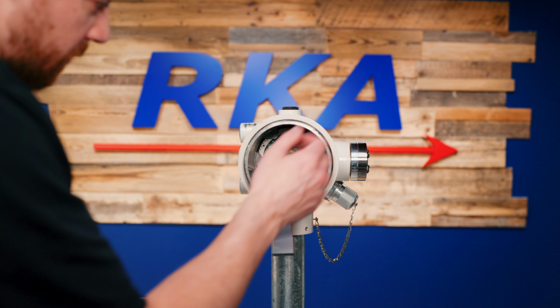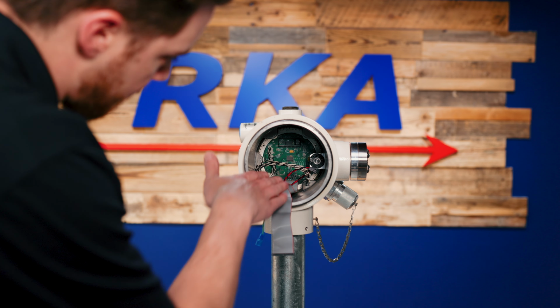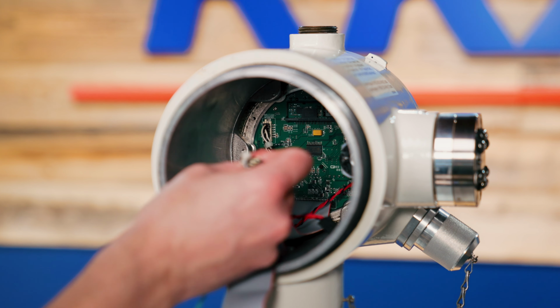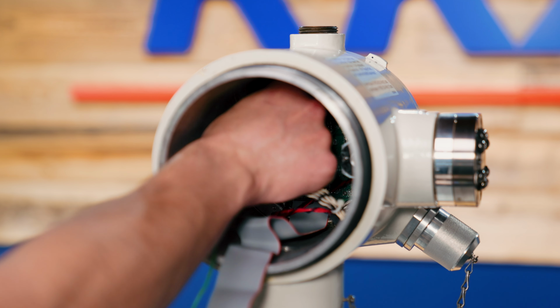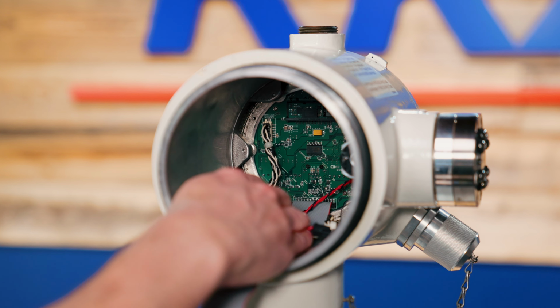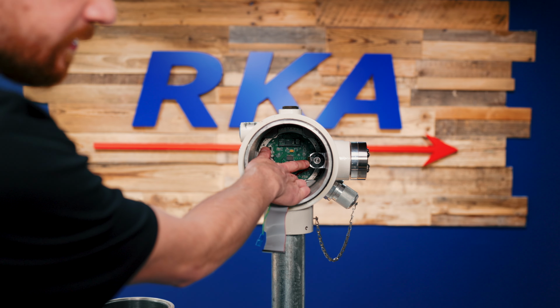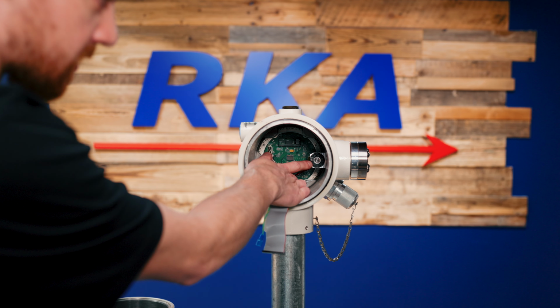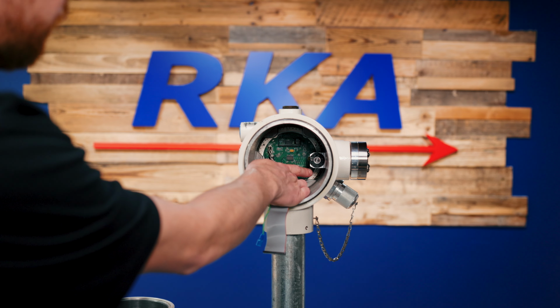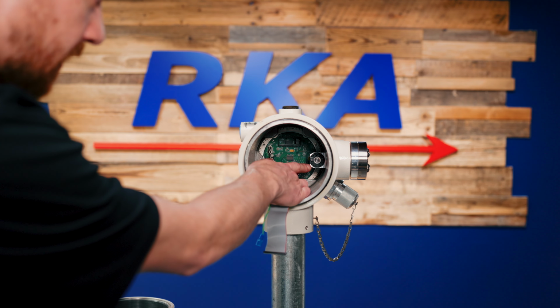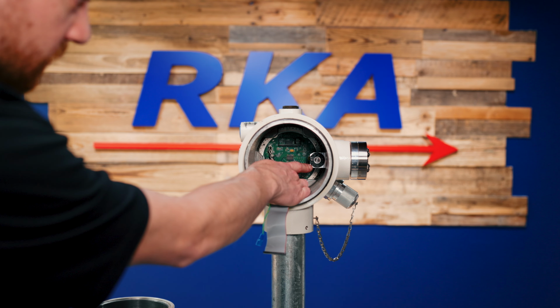A couple things before we put in the new module. You'll want to verify that your ribbon cable and your rear term cable are still in their connectors on the rear termination board. You'll also see there's a gasket here on the feed-through. Sometimes this stays on, sometimes it comes off when you remove your module. You want to make sure that this stays on or you replace it with the new one in the box that comes with the module.